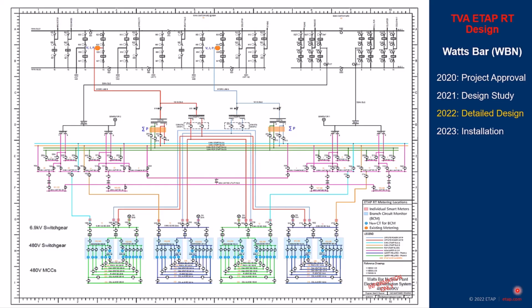And I know you can't read everything because it's zoomed out so far, but that's okay. The point I want to make is my critical electrical systems are down here. This is what we call the Class 1E system. This is my switchyard for the nuclear plant and a nearby switchyard of a hydro plant, and my offsite power actually comes from the hydro plant. The orange that you see here are existing data. So I do have some existing data points, voltage, current, and power coming from the hydro plant, offsite power circuit feeder, and I also have a summation of power data on these transformers.